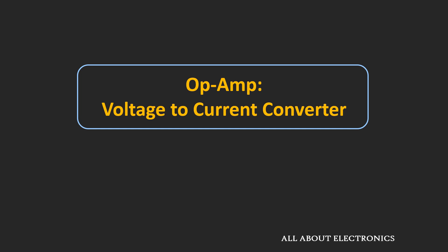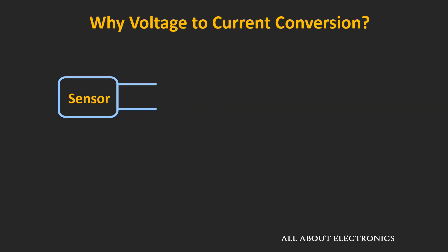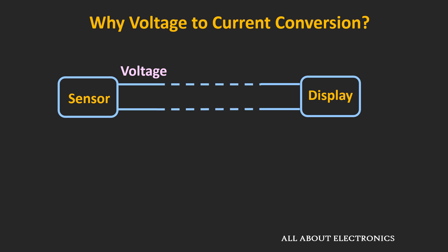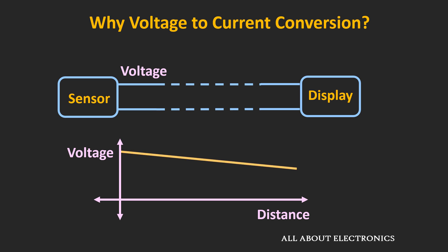Before we understand that, first of all let us understand what is the need of this voltage to current conversion and why these types of circuits are used. This type of circuit is particularly useful in industrial applications as well as in instrumentation. Let's say you are measuring some parameter like temperature using a sensor, and the sensor is giving output in terms of voltage. In industrial applications, it is quite possible that the location where the sensor is measuring that parameter and the location where the value is being displayed are quite far away from each other. The voltage generated by the sensor needs to be transported to the other end, and you will find that there will be a drop in the voltage, because during transportation there will be a voltage drop across the cable. Moreover, it is quite possible that noise will get superimposed over this voltage. So this is the basic problem in industrial applications when you are dealing with voltages.